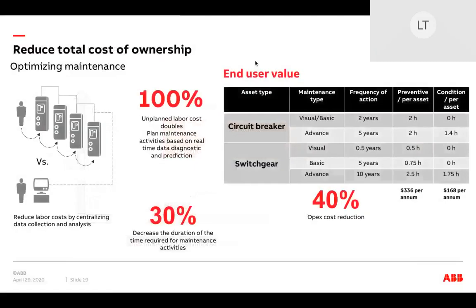So how does ABB Ability help you? Let's look at operational cost. A maintenance manual, let's say, might say every 3 years you need to do a breaker timing check. With condition monitoring, you can collect that every time you switch and centralize the data, therefore reducing cost per asset for maintenance. If you look at the effect in terms of direct optimizing of cost, it will give you a decrease of duration time for maintenance activities of around 30%. It can give you an OPEX reduction cost of around 40%, but more importantly, it can give you 100% unplanned labor cost reductions.